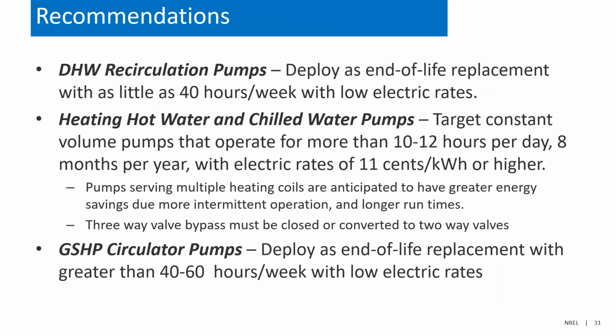So some of the recommendations here is essentially deploying these as end-of-life replacements. We did look at the installed cost as the delta between a standard pump and this high-performance circulator pump. I think for all the facility managers, though, first step is to target your domestic hot water recirculation pumps. We found even with very low electric rates and 40 hours a week of operation, they should be cost effective. For heating hot water and chilled water pumps, you want to make sure that you're selecting pumps that have sufficient runtime. So we're targeting 10 to 12 hours a day, roughly 8 months a year.